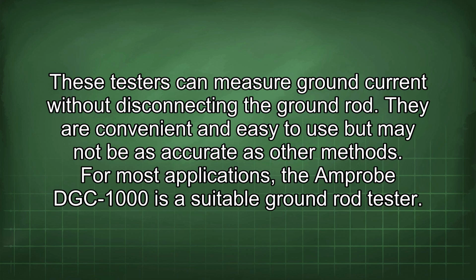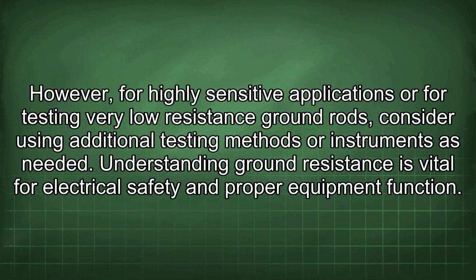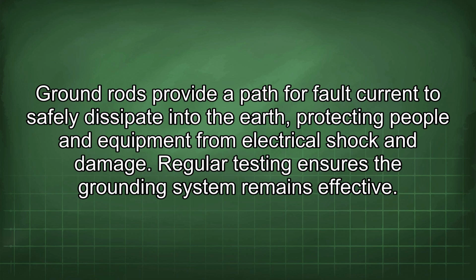For most applications, the Amprobe DGC-1000 is a suitable ground rod tester. However, for highly sensitive applications or for testing very low resistance ground rods, consider using additional testing methods or instruments as needed. Understanding ground resistance is vital for electrical safety and proper equipment function. Ground rods provide a path for fault current to safely dissipate into the earth, protecting people and equipment from electrical shock and damage. Regular testing ensures the grounding system remains effective.